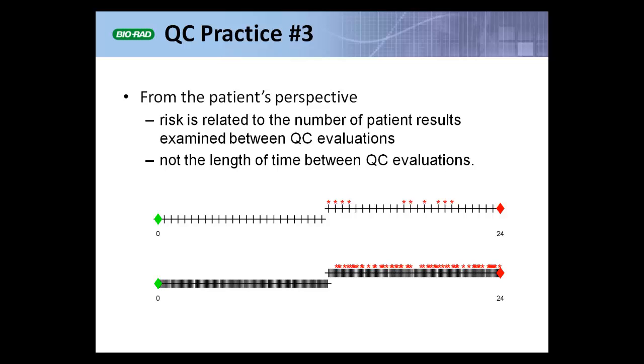The little red asterisks are meant to denote patient results that fail to meet their quality requirement. In these two situations, the interval between QC testing is the same — 24 hours — but in the lower cartoon, many more patients are tested between QC events. The fraction of red asterisks in the two cases is the same, but there are many more red asterisks in the bottom cartoon than in the upper cartoon.